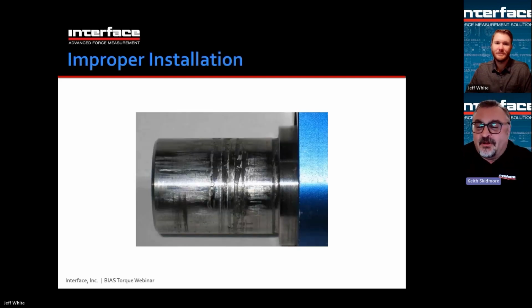So this is what happens when, say, an improper coupling is installed. This is actually a customer who made their own coupling, and they used a set screw by drilling a hole through the coupling hub and tightening the set screw against the sensor shaft. Well, what happened? It slipped. Guess what happens? As soon as it slips a little bit, it keeps slipping. And so here the set screw spun round and round on the shaft end. And this basically ruins the sensor.